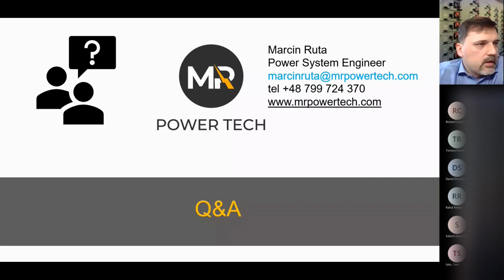Question from Jerome. Regarding the maintenance mode of the CB enabling arc flash mitigation, I believe that the certification body has to approve the solution, I guess because this affects the overcurrent protection of the electrical system. Not that I know. The certification body will approve, for example, the breaker and the type approval, but it has nothing to do with the protection. So you adjust your protection based on your system. It depends what the system is.